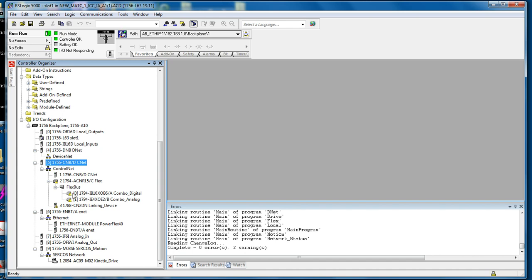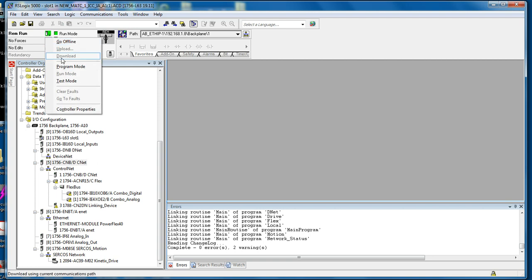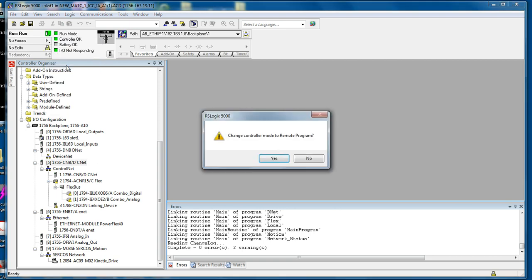These yellow exclamation marks mean there's something not working in these units. Since it's all of the items after this ControlNet card, it is very likely that the ControlNet has not been scheduled. In order to do so, we're going to go into program mode.